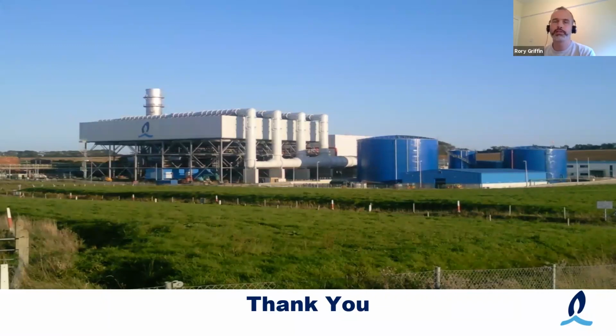What is the annual maintenance for the boiler, turbine, generator? Does maintenance incur much downtime annually? So it depends. There's two things that drive the outages. One is what stage you're at on, say, the gas turbine with your intervals. Every 24,000 hours, you'll have to go into a hot gas path inspection. And every 48,000 hours, you're into a major inspection. In the years in between, it's just a 1-week borescope inspection. So that's one aspect of it.